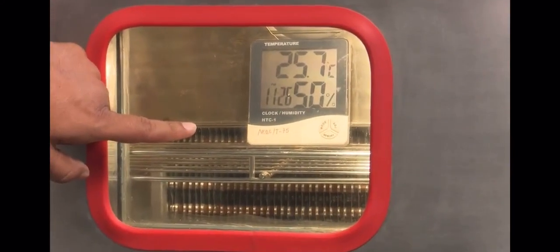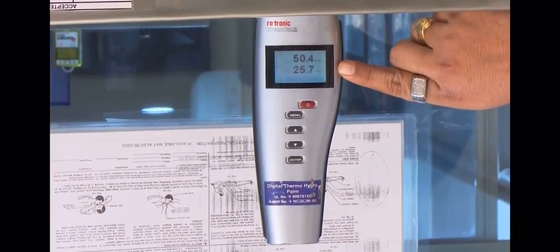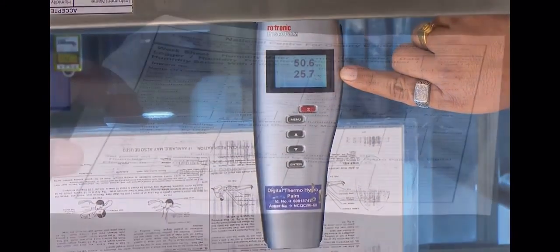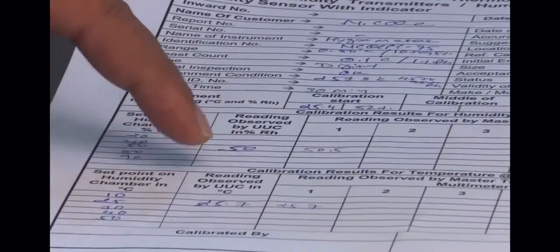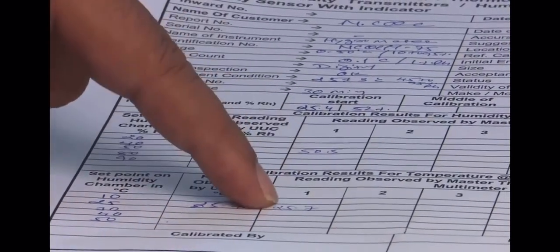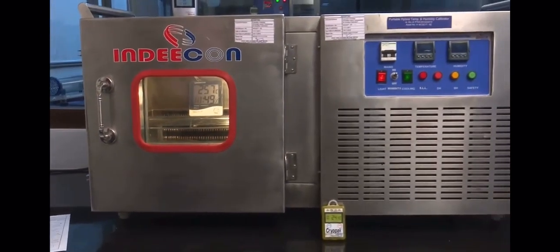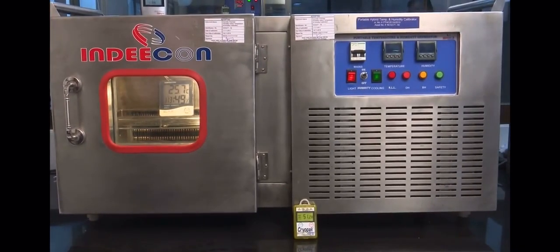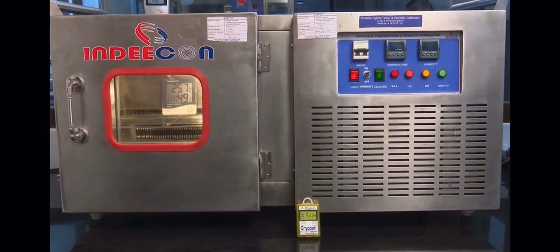Switch on the lamp inside the environment chamber and read the values shown by UUC and thermohygrometer. Note down this reading in the worksheet. This is called first calibration point. You have to repeat for 4 more times to complete the calibration for this point. In this way, the demonstration of calibration of digital thermohygrometer for one point is completed for this training purpose. You have to do this for all the points as per the method.